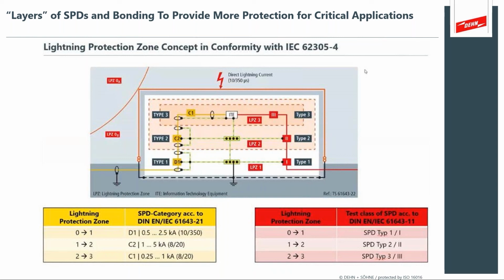Well, my personal preference is that the SPD has its own home run connection back to the master ground bar. What you see a lot is a point of use device, like a power strip that your computers and your expensive home electronics are plugged into. That type of device protects relative to the ground wire in the power strip. That is effective, but it's not ideal because you're dumping those surge currents back into your ground and your neutral wires. Although it's very complicated, it would be better to have a dedicated home run back to the master ground bar. It's just not practical in many applications.